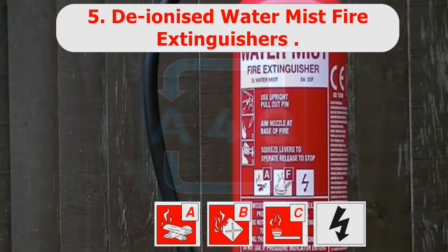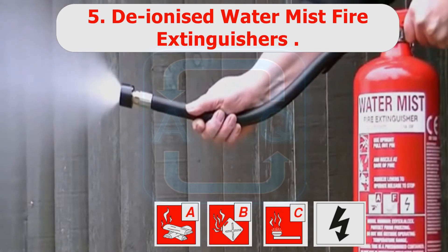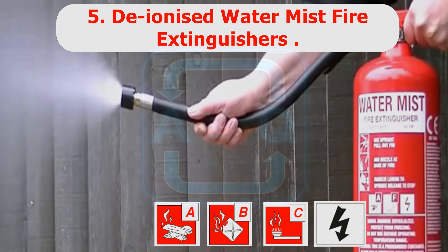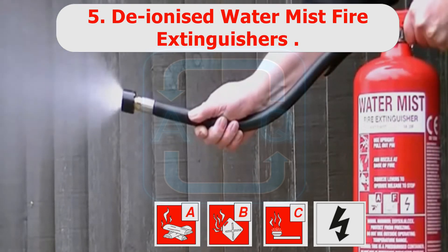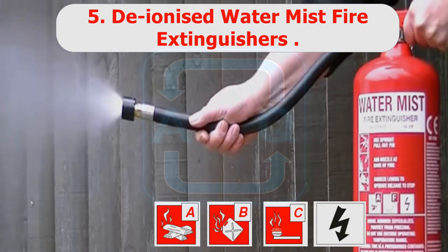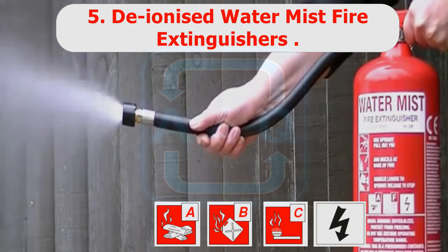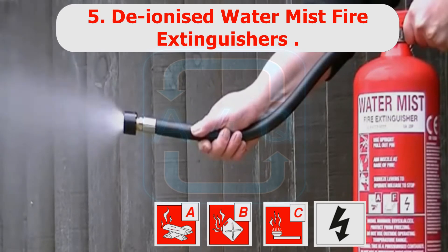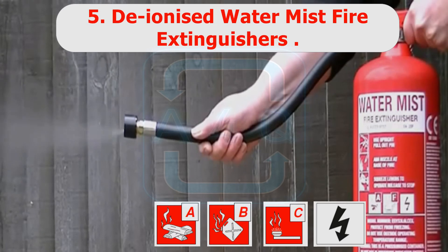Deionized Water Mist Fire Extinguishers have a white label and are highly effective on Class A, B, C, and burning electrical equipment. The unique supersonic nozzle creates a microscopic mist curtain, reducing the oxygen content. They are safe for use on electrical equipment as the deionized water mist does not conduct electricity and does not form puddles which could lead to electrocution.